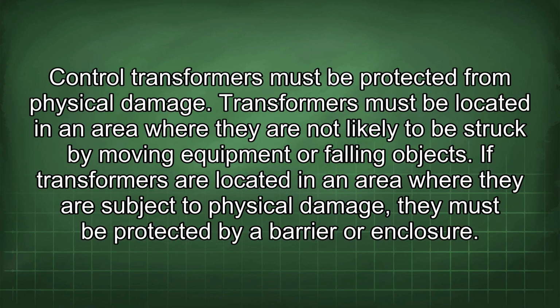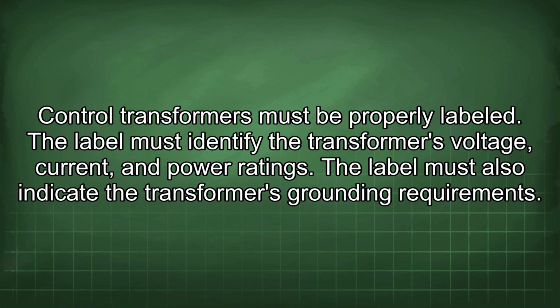Control transformers must be protected from physical damage. Transformers must be located in an area where they are not likely to be struck by moving equipment or falling objects. If transformers are located in an area where they are subject to physical damage, they must be protected by a barrier or enclosure. Control transformers must be properly labeled.